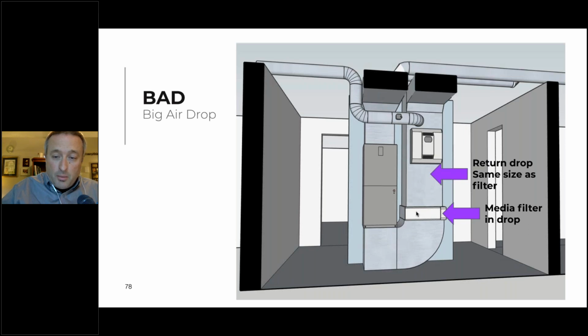A nice thing about putting the filter here is the air comes down at pretty low velocity, and low velocity is better for filtration. You don't want to cram the air through the filter—you want to let it slow down and take its time. It also hits the whole surface equally, or nearly equally, much more so than if you put it down here.